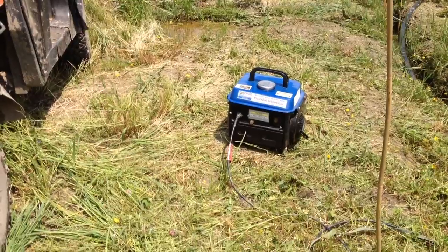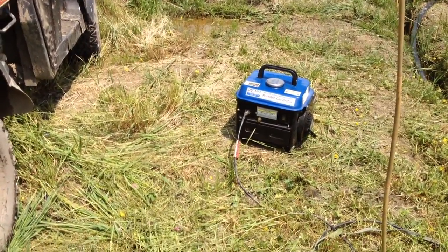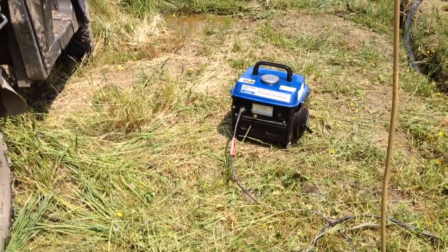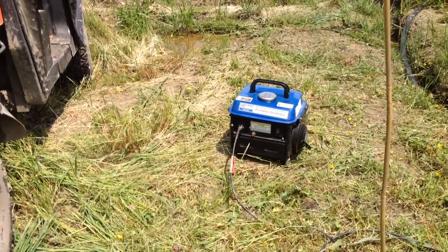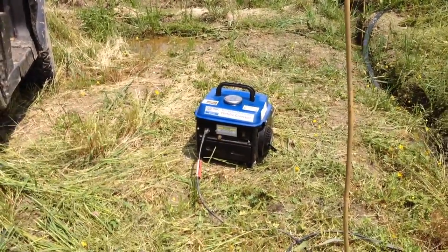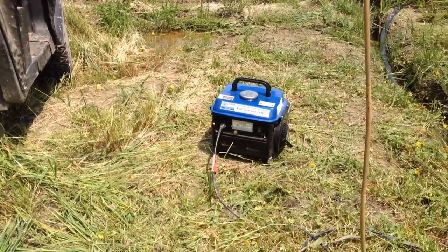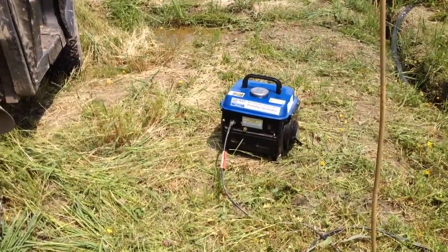So again: check the strength of the outlet. If it's popping the breaker all the time, hook up some light bulbs to the rated power. If it's still tripping, change the breaker — they're kind of crappy, and complaining won't do any good. Get yourself a new breaker. And after about four or five years, when the voltage starts to go wacko, just replace the capacitor. It will cost you less than $10 and you'll get years of service out of it.